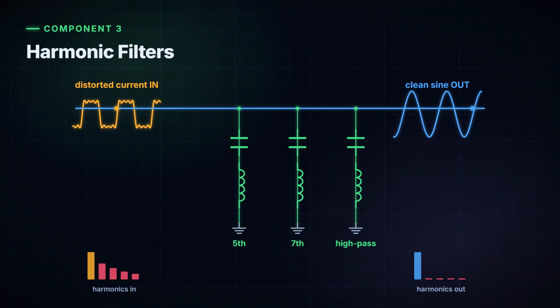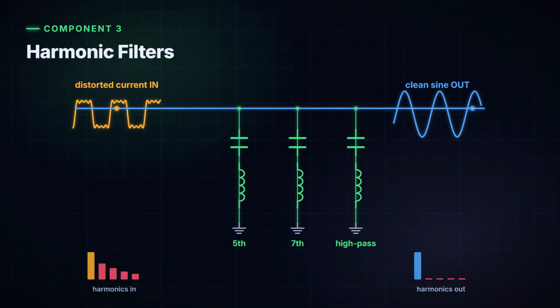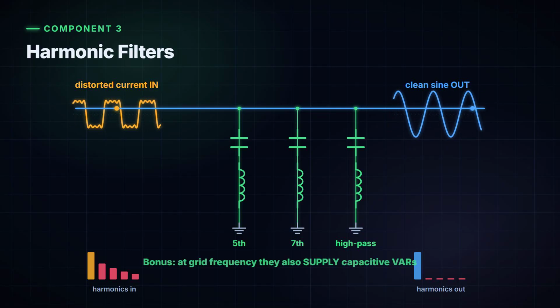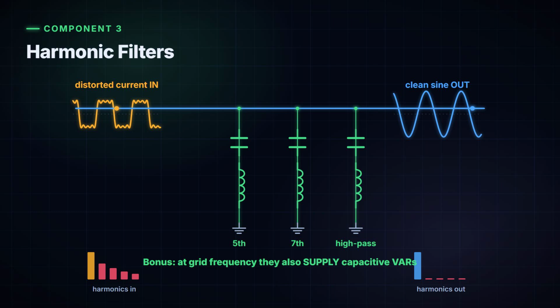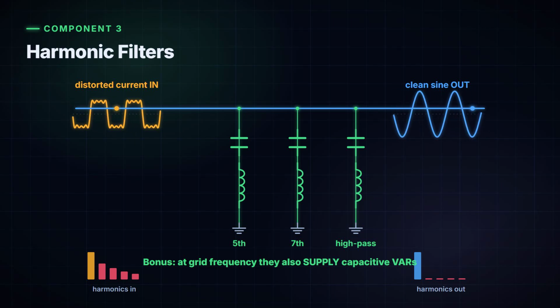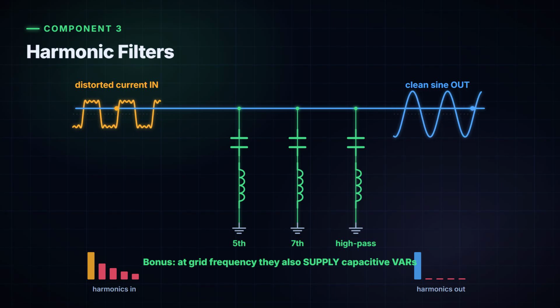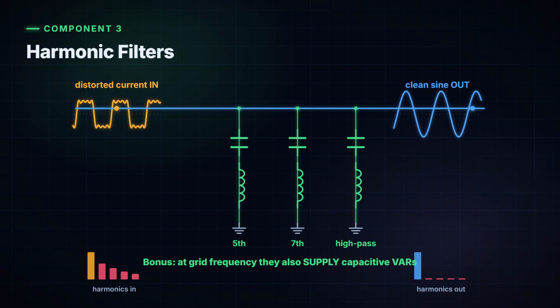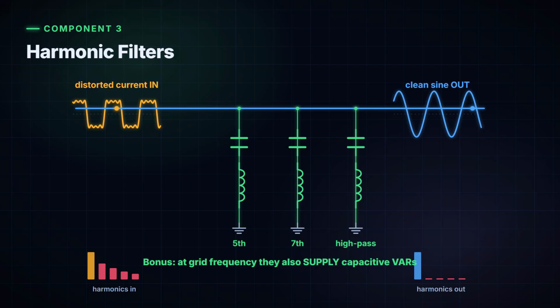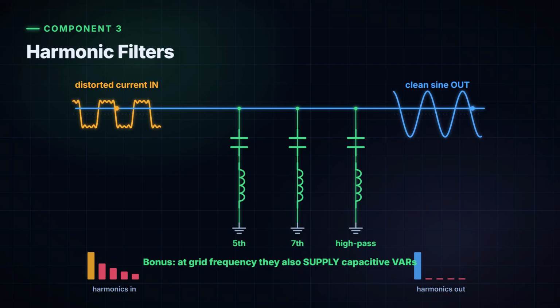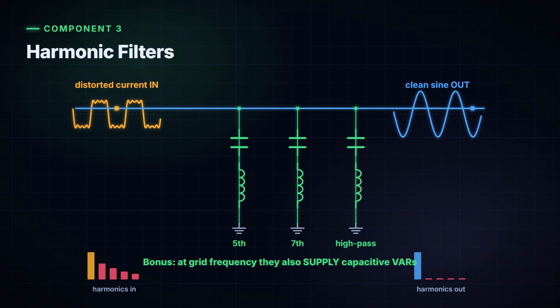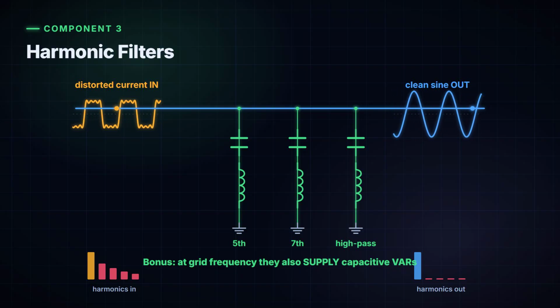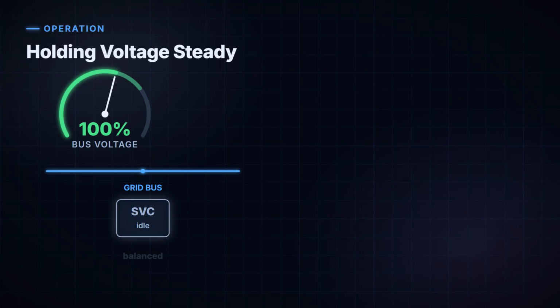Watch the waveform. Distorted going in, clean sine coming out. But these filters earn their keep twice. At the normal grid frequency, a capacitor naturally supplies reactive power, so on top of cleaning the signal, the filters also act as a permanent source of capacitive VARs, doing useful work all the time, not just when there's a harmonic to absorb. So now we have all the pieces.